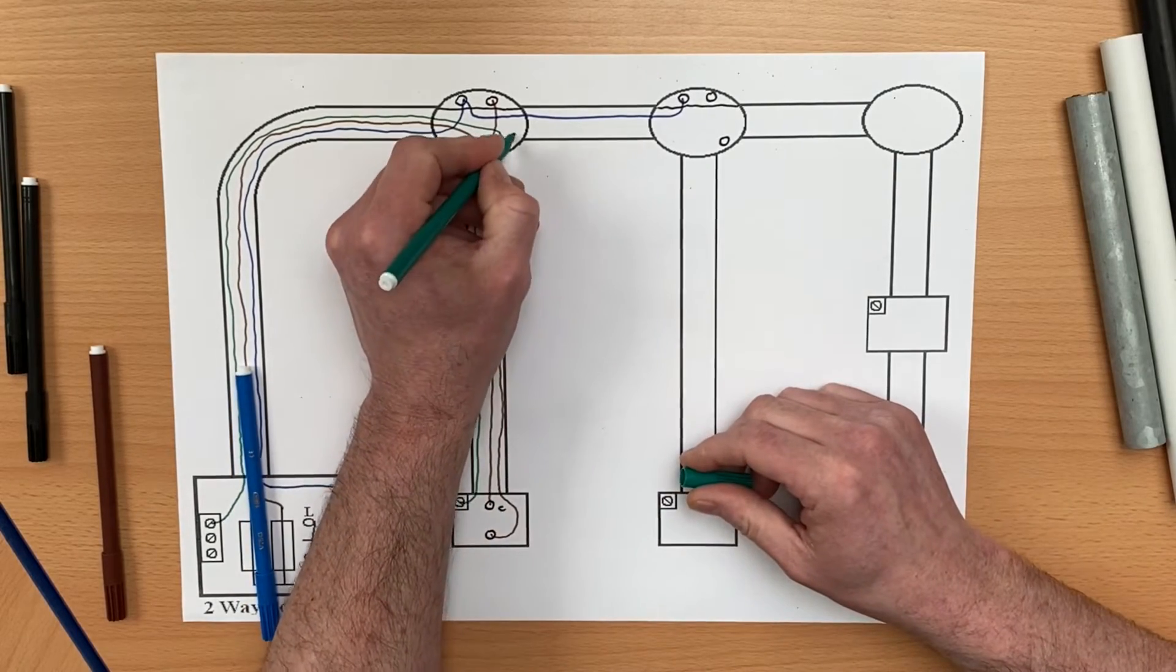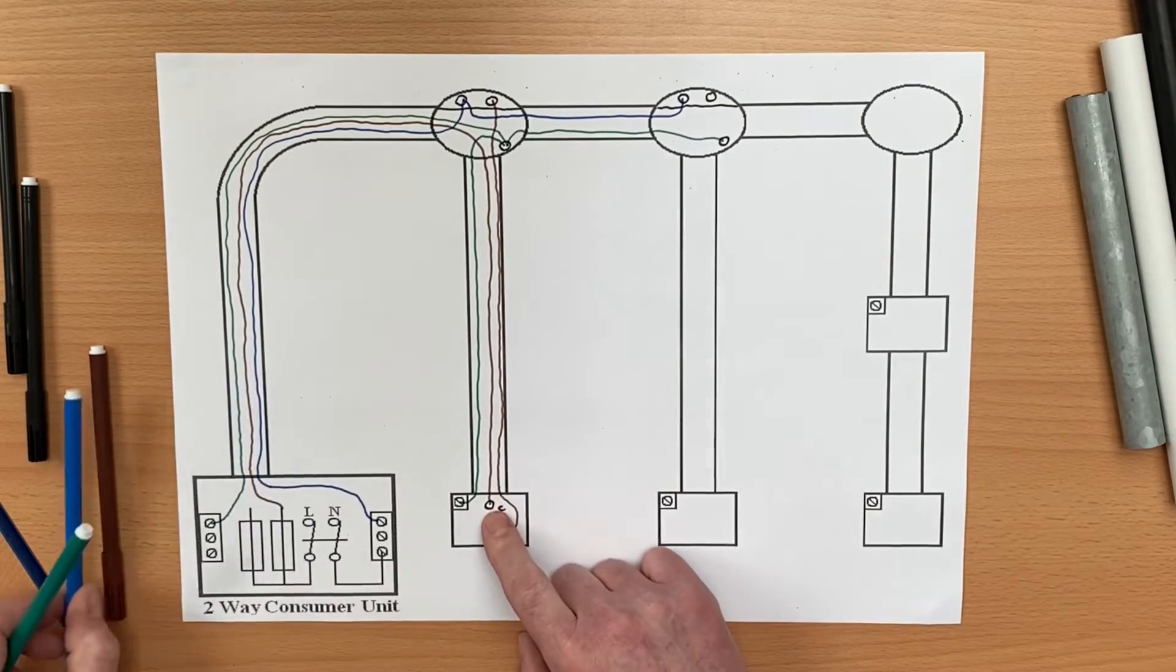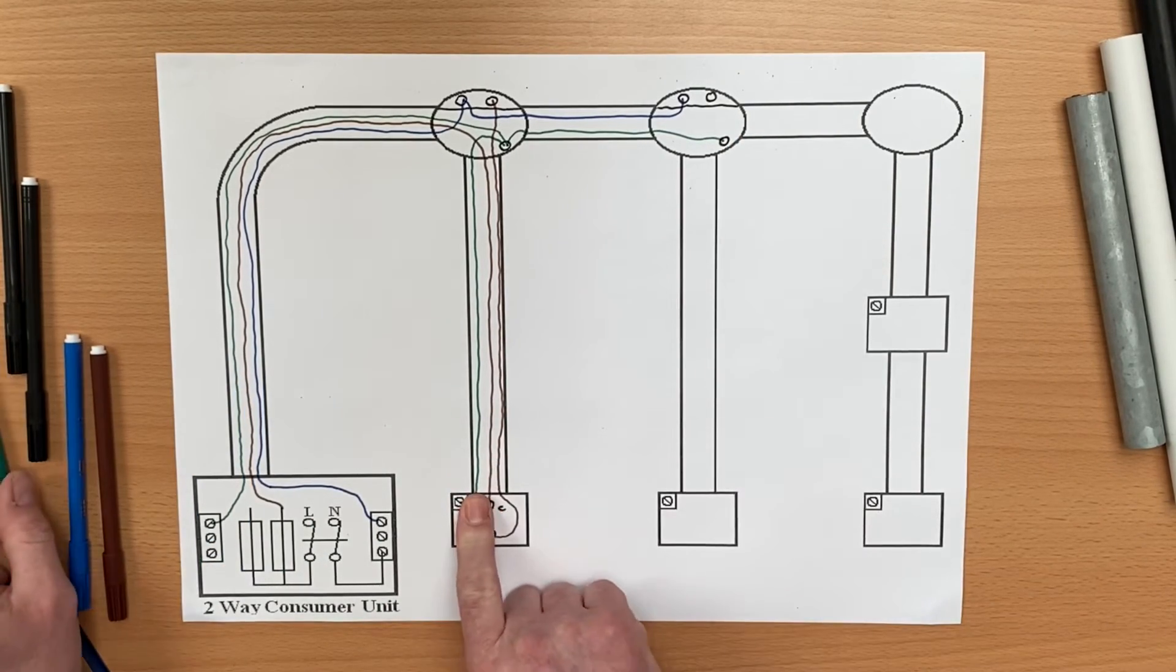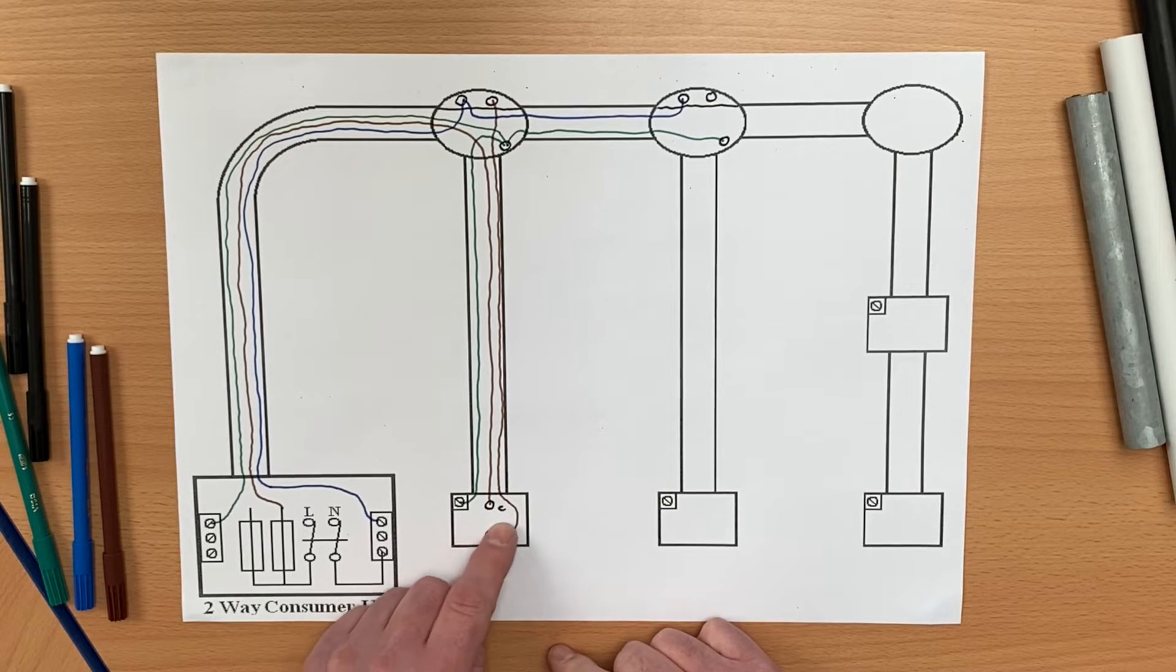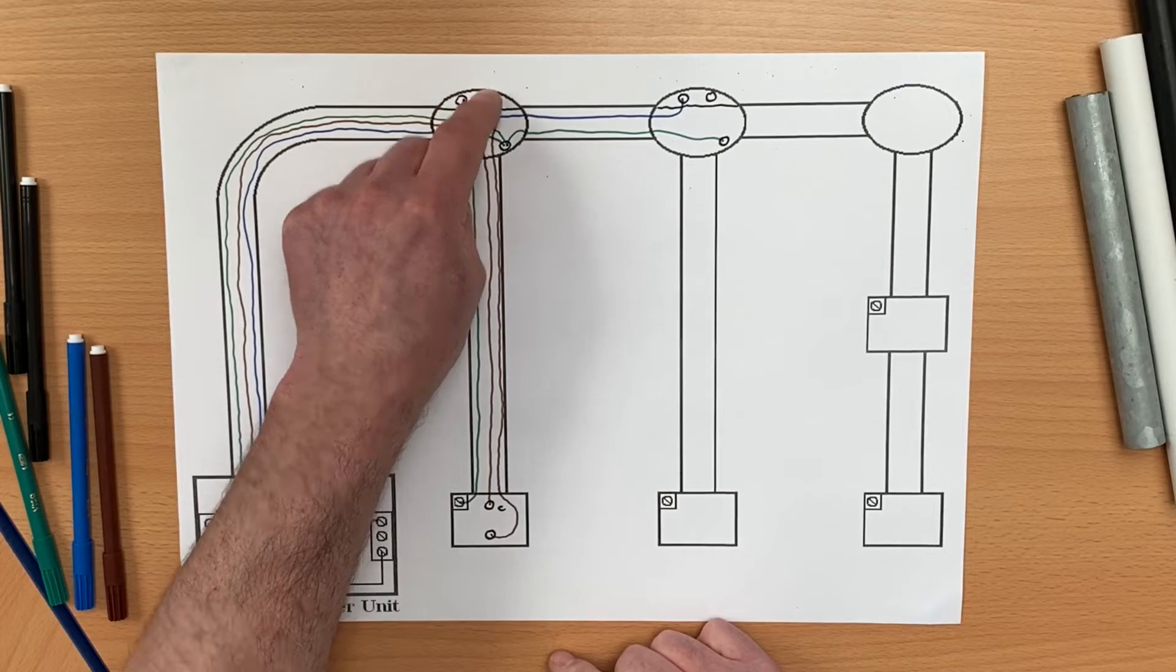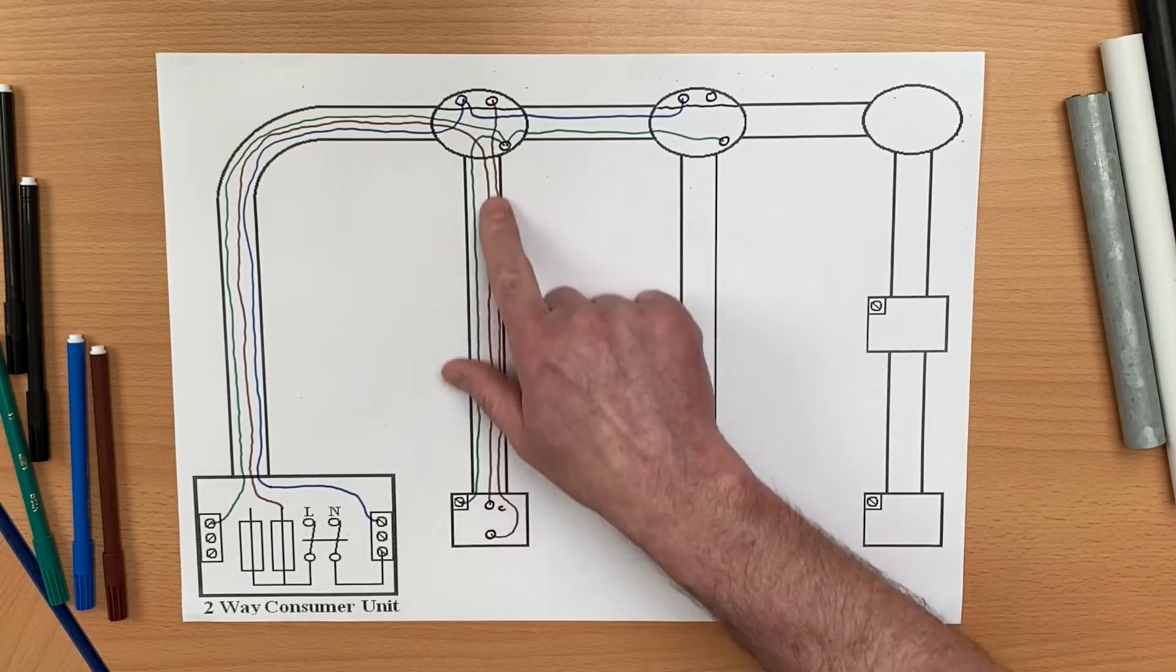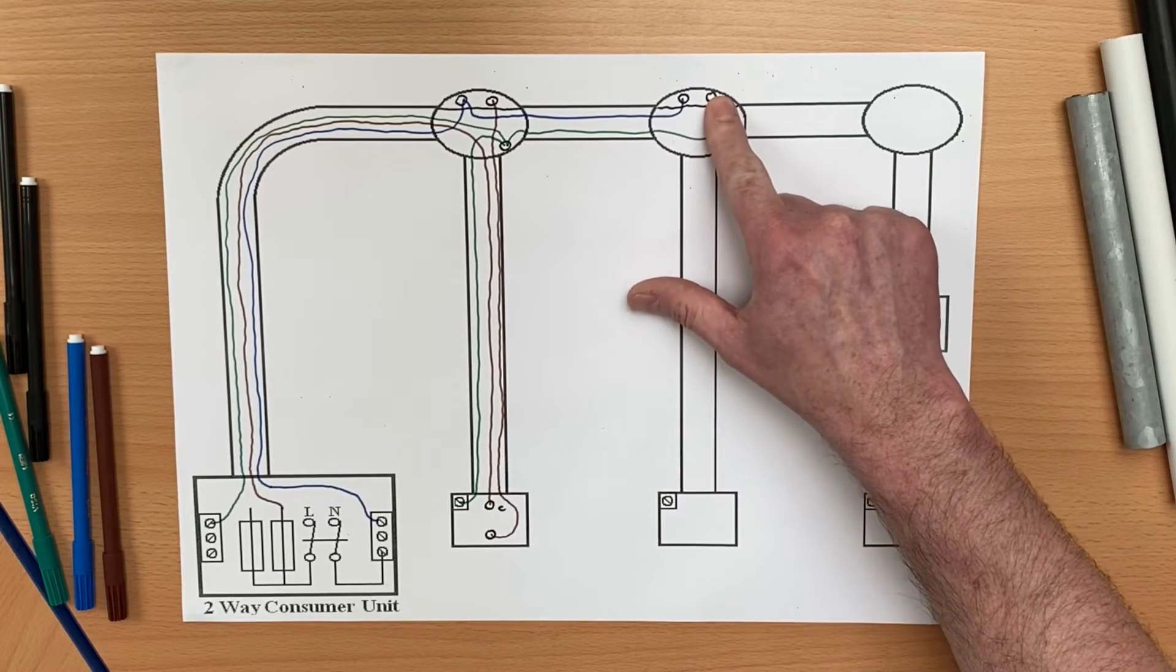Where's the CPC? Where's the closest CPC that we can get? Well the closest CPC is here, so let's bring that one through. Now we've got to work out: when we turn this one on, when we close this switch, we put a switching line here onto L1 that comes up and turns on this lighting point here. We could take our switching line from here, come up to the conduit and through to this lighting point just here.